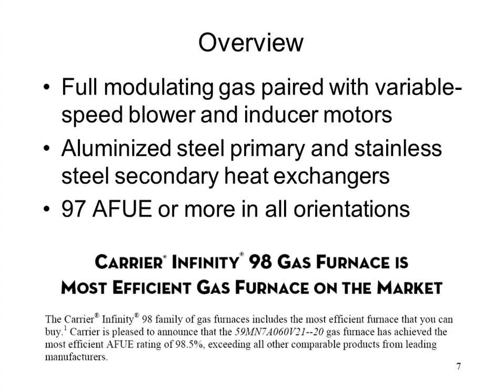On these modulating gas furnaces, they are 97% AFUE in all orientations at a minimum, and sometimes even higher, up to 98.5% for the size 60,000 BTU version. So the worst is going to be 97, the best is going to be 98.5, and it's all orientations, meaning upflow, downflow, horizontal left, horizontal right.